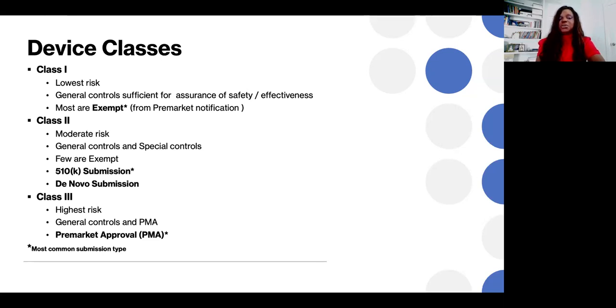But then there are special controls, and these special controls are usually device specific. I'll go into the different types of controls just so you see how they work and which ones would be applicable to your device. A few of these class 2 products may be exempt, but they may have been down classified by the FDA. They may have been initially class 2, but now they're class 1 exempt. But generally speaking, all class 2 devices require a 510(k) pre-market notification submission to the FDA.